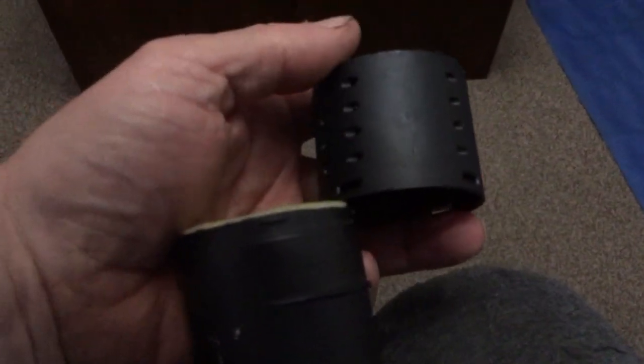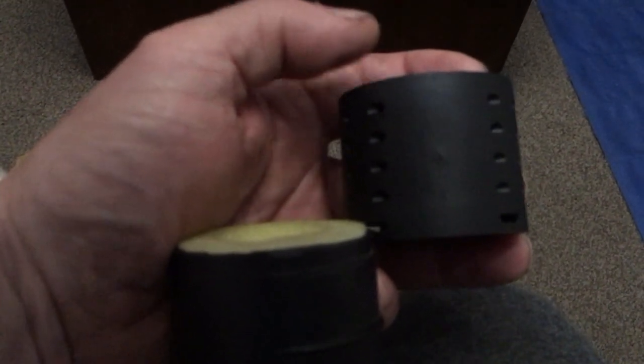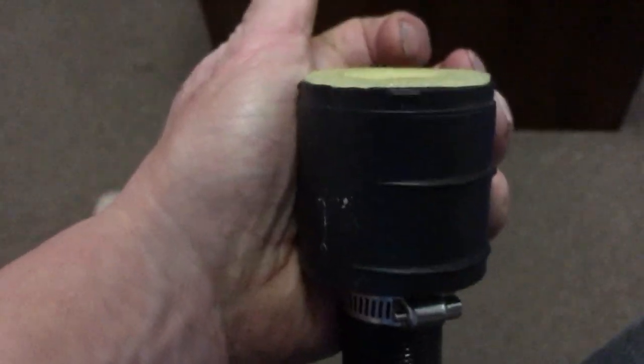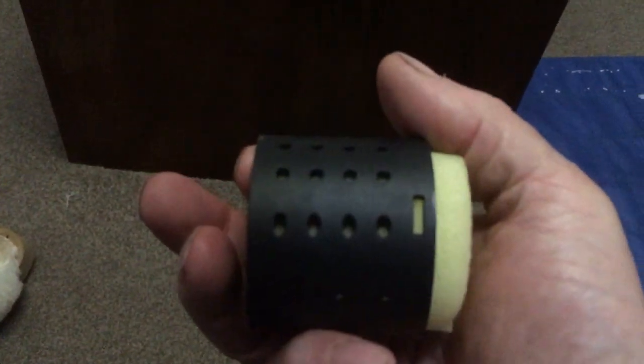So in effect, it ain't actually doing anything. If I turn that round the other way — if that wasn't on it, it'd actually sit about there. So all it's doing is the air is going through these holes here and straight down the middle of that pipe. None of it is going through that foam. I'm presuming it's supposed to sit like that, packed up to the top, if you can see through the holes.